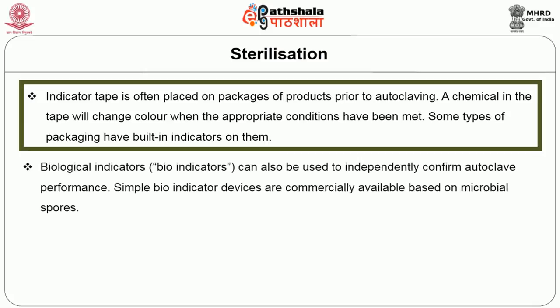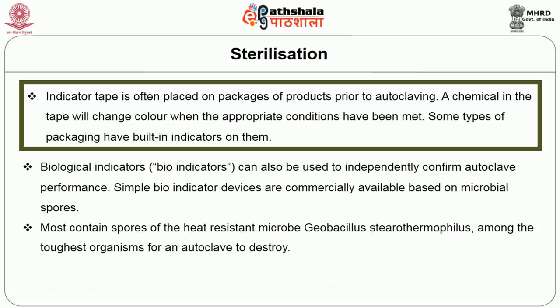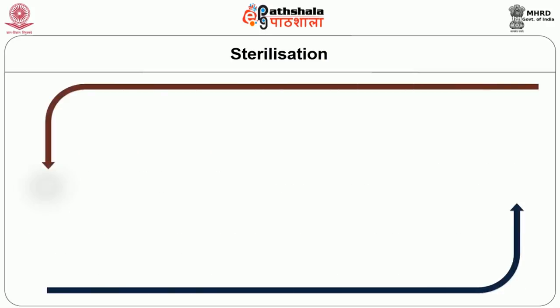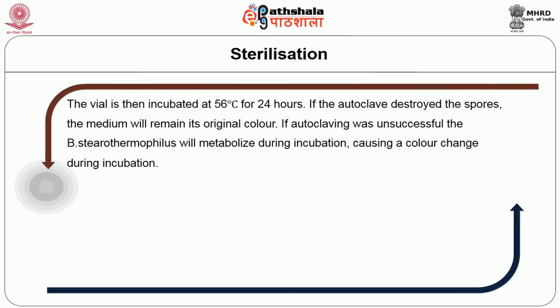Biological indicators can also be used to independently confirm autoclave performance. Simple bio-indicator devices are commercially available based on microbial spores, most containing spores of the heat-resistant microbe Geobacillus stearothermophilus — among the toughest organisms for an autoclave to destroy. Typically these devices have a self-contained liquid growth medium and a growth indicator. After autoclaving, an internal glass ampoule is shattered releasing the spores into the growth medium. The vial is then incubated at 56 degrees Celsius for 24 hours. If the autoclave destroyed the spores, the medium will remain its original color; if autoclaving was unsuccessful, the Bacillus stearothermophilus will metabolize during incubation causing a color change.